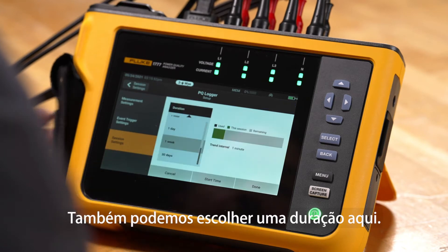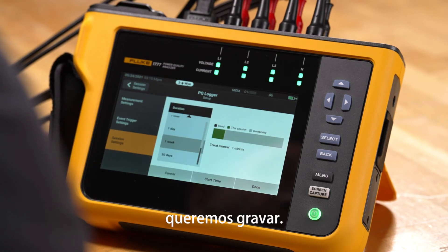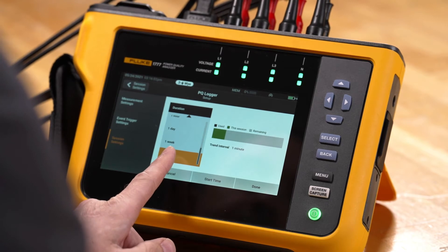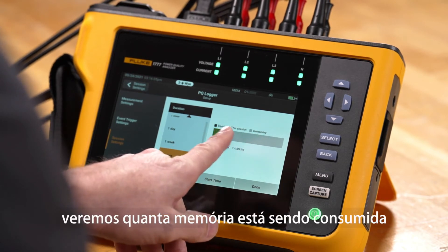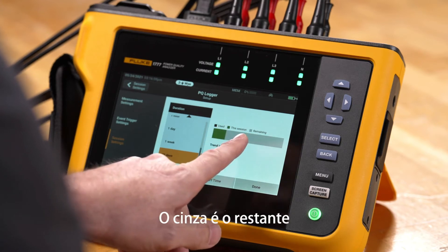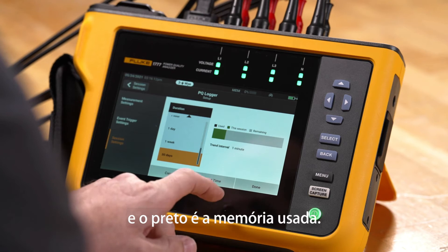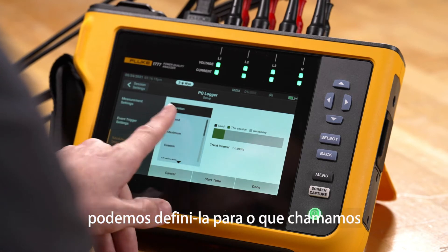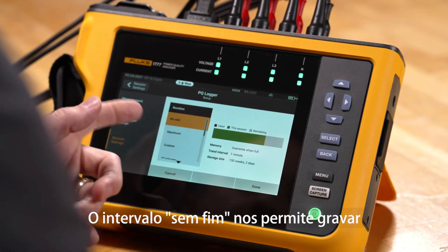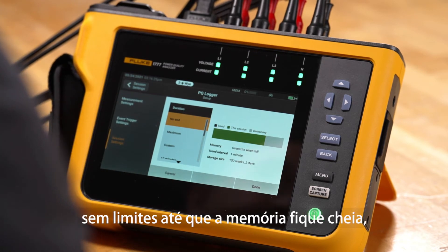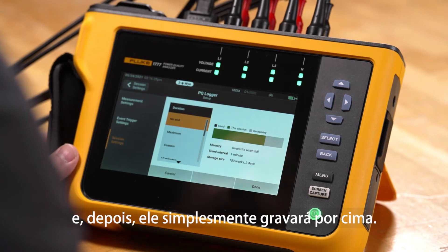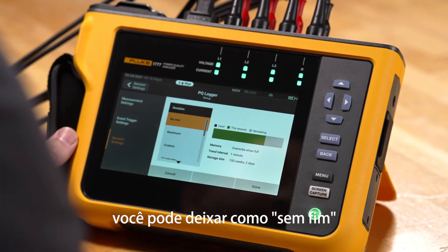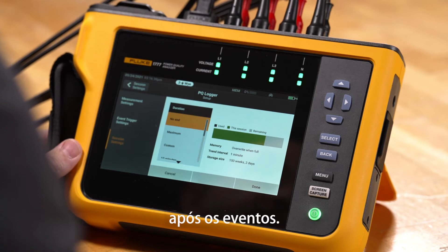We can also pick a duration here, which allows us to pick how long we want to record for. There are some presets — let's pick 30 days for example. In this menu we'll see how much memory is being consumed by the recording in green, the gray is the remaining, and the black is the used memory. We'll also see our current trend interval, which is one minute. In the duration we have the ability to set it to what we call no end, which essentially allows us to record limitlessly until the memory fills up and then it would just overwrite itself. This way, if you need a semi-permanent or permanent recording installation, you could put it into a no-end configuration and leave it there, coming back when you need data after an event has occurred.